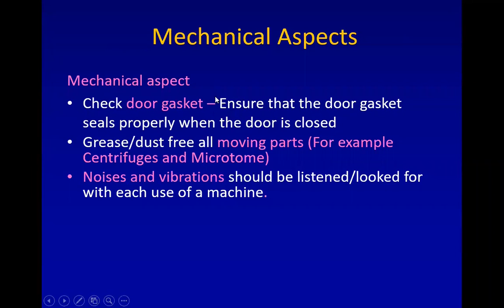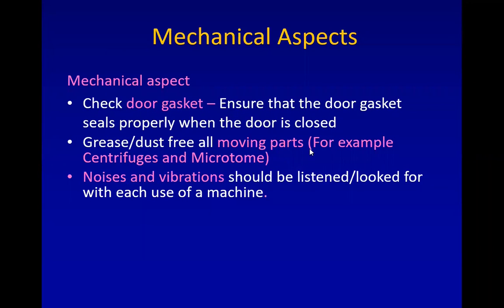Regarding mechanical aspects: the door gasket should be checked so that the door fits and closes properly. Certain equipment have moving parts which should be dust-free; grease or machine oil can be used for moving parts. Examples of instruments with moving parts in a clinical laboratory are centrifuges and microtomes. If there are unusual noises or vibrations from the equipment, it should be inspected by a service engineer.